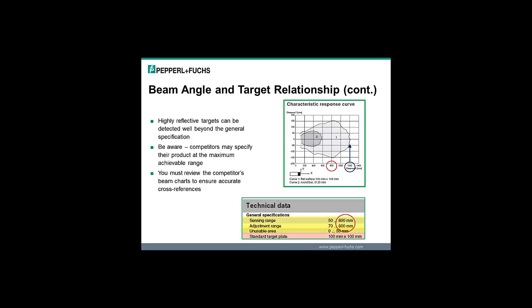And you should be aware that a lot of competitors will not allow for this excess gain. They'll specify their sensor at the absolute maximum distance. So if you're doing a cross-reference for ultrasonic sensors versus one of our competitors, make sure that you look at their beam chart to see if their version of a UB800 really maximum is 800 or if it goes out to 1200. Sometimes the cross-references can be a little tricky because of the way different manufacturers specify their sensing ranges.